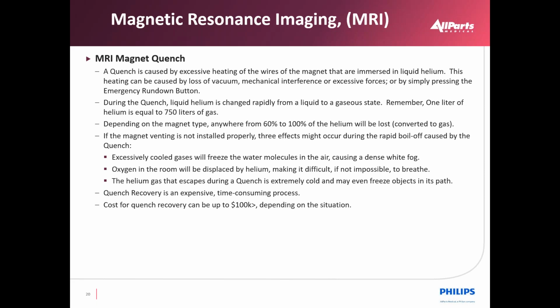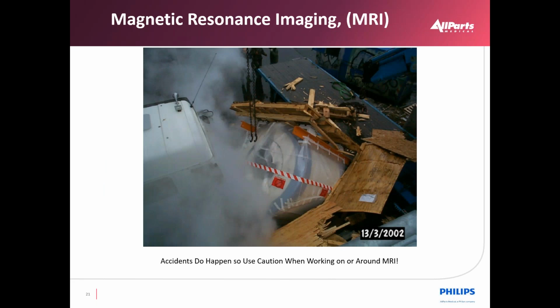To prevent damage to the magnet, there are specialized discs in line with the magnet vent called burst discs. They're usually made from a ceramic material and are rated to fracture or break under high pressure. This allows the helium gas to escape while keeping the magnet safe from damage. A quench recovery is a costly process and can range up to and over $100,000 to bring the magnet back to scanning capabilities. There are many examples of MRI quenches that can be found on YouTube. Accidents can happen, so please use caution when working around an MRI.